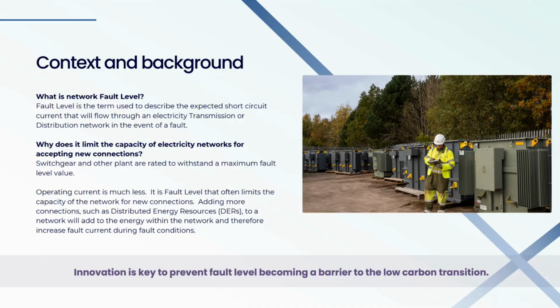But for that short space of time between the fault occurring and the network protection systems operating, the network itself needs to be able to cope with that big surge of energy, that fault current flowing through the network. That fault current is much, much higher than normal operating current. So the switchgear and other plant on our network, transformers, circuit breakers, cables, cable joints, and so on, all need to be rated to withstand a maximum fault level value. And as we connect more and more connections to the network, particularly distributed generation, that's pushing up network fault level. As a result, it's fault level that often limits the capacity of the network for new connections.